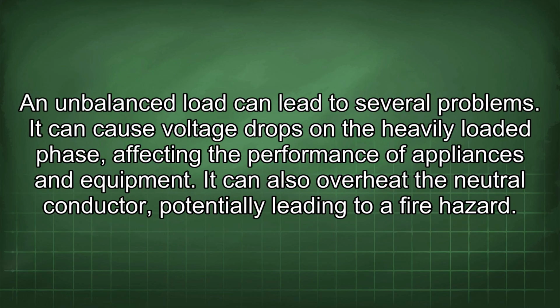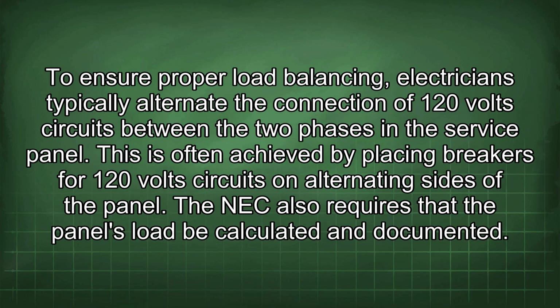An unbalanced load can lead to several problems. It can cause voltage drops in the heavily loaded phase, affecting the performance of appliances and equipment. It can also overheat the neutral conductor, potentially leading to a fire hazard. To ensure proper load balancing, electricians typically alternate the connection of 120 volt circuits between the two phases in the service panel. This is often achieved by placing breakers for 120 volt circuits on alternating sides of the panel.